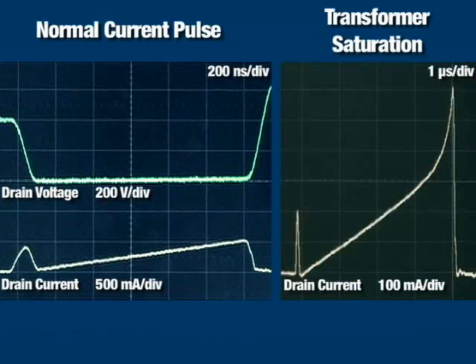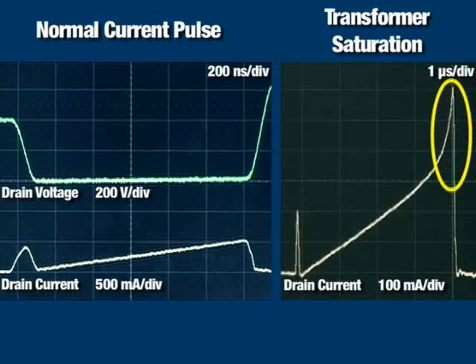During startup, you may see one of these two current waveforms. The current waveform on the left is a normal current pulse that ramps linearly from turn on to turn off. The current pulse on the right shows signs of transformer saturation. Notice how this pulse becomes somewhat exponential towards the higher end. This is where the transformer core saturates and can no longer store energy.